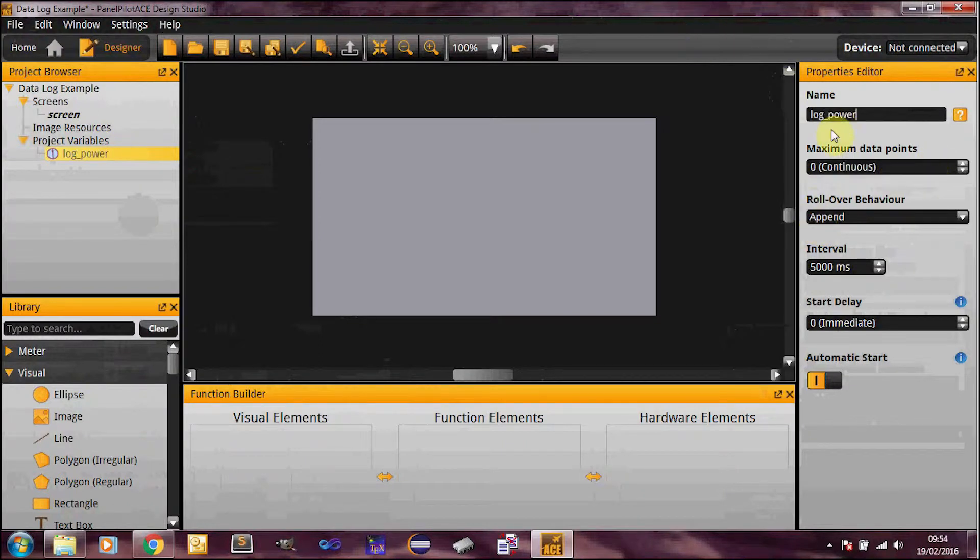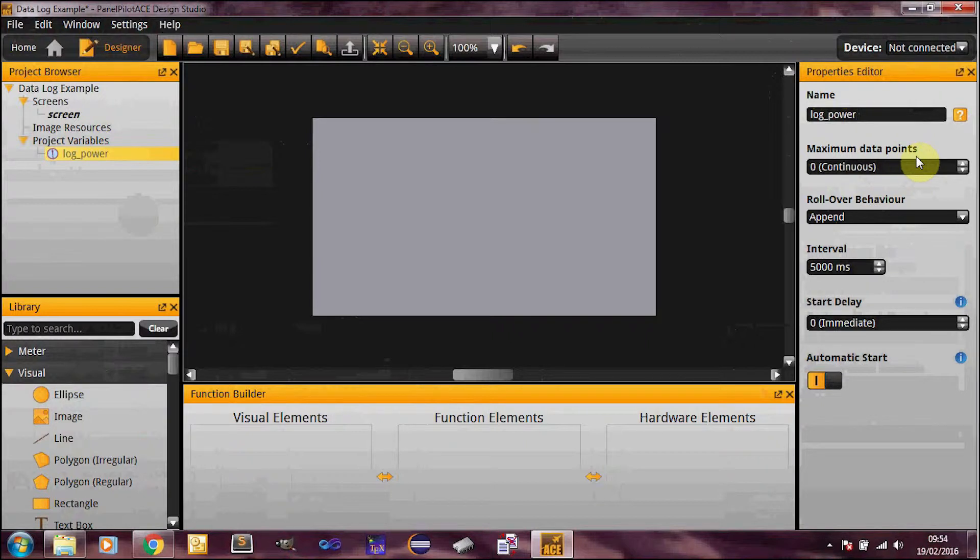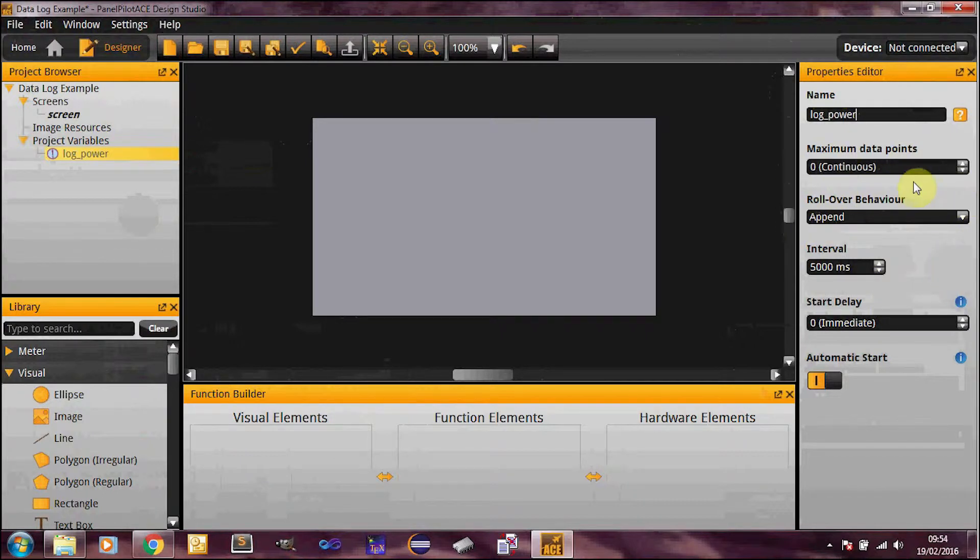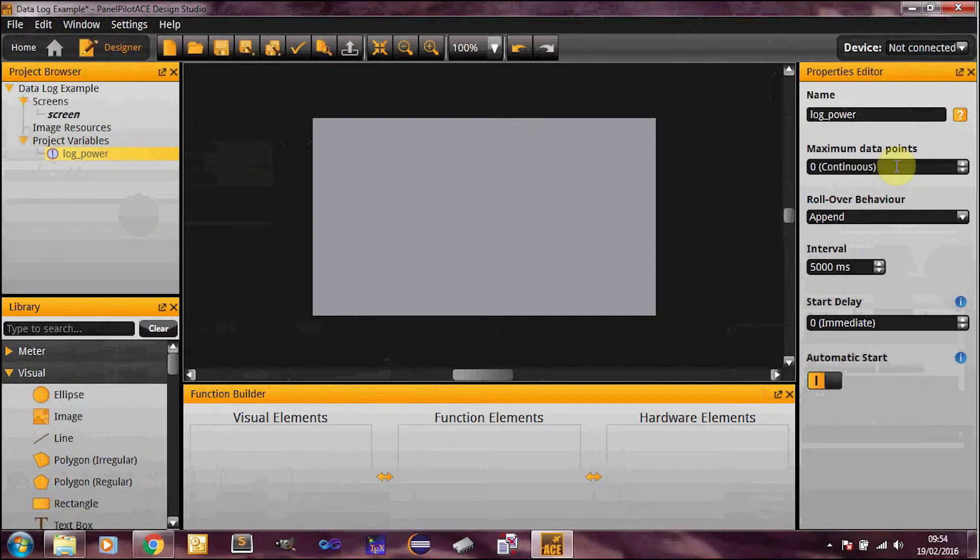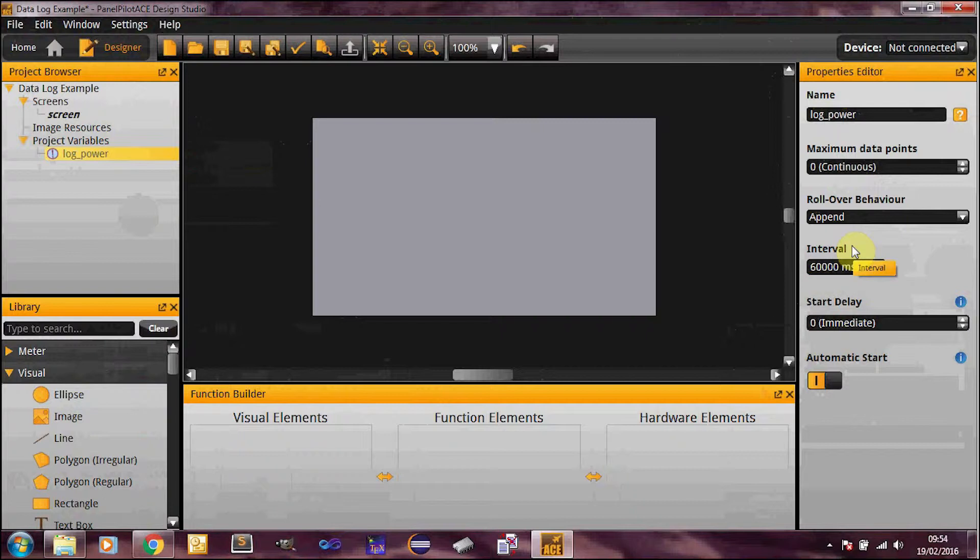So the name is standard as per all the other elements. It's your maximum data points. So what this is specifying is how many data points you can physically have in this log before it does whatever you specify in the rollover behavior. So you could have an unlimited number of data logs. Or if you're interested in say the last days information, you could set this up appropriately. I'm going to specify the last day. I think it sounds pretty reasonable. Obviously that's going to depend on your interval here. So these work in basically the same way as a timer. If you're familiar with a timer. So I want, let's have one minute logging. So 60,000 milliseconds, 60 seconds, that's a minute.